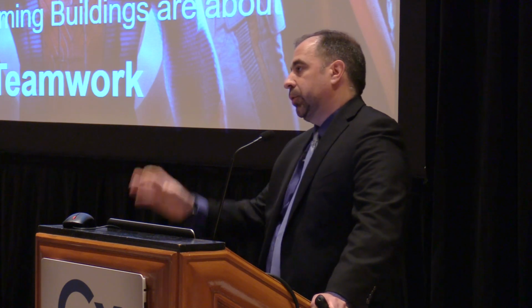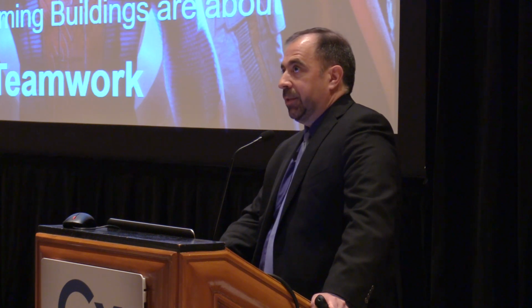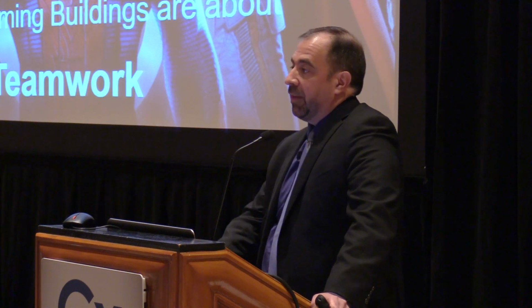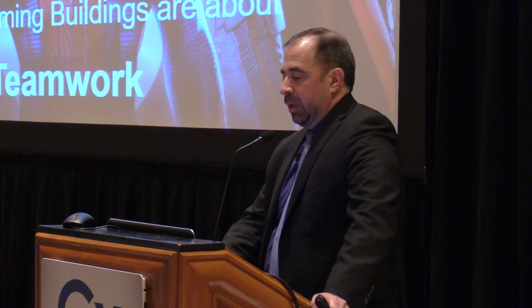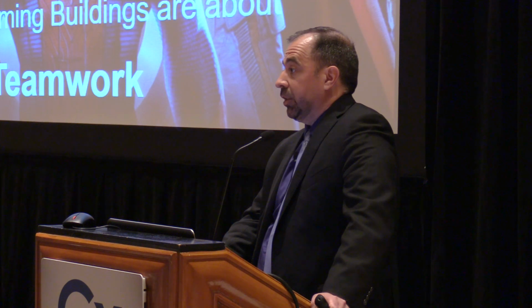ASHE, the American Society for Healthcare Engineering, has an emergency generator testing monograph - it's basically a guide. Are you using anything like that when developing your procedure, like a checklist of everything that needs to be tested? Yes, is the short answer. There's also the health facility commissioning guidelines that ASHE put out, which we reference for what should be commissioned in a hospital. I'm a big fan of that document because they want to test everything under the sun. I haven't referred to it in a while, but inherently we're trying to test to all those things, or at least ask those questions to make sure somebody tells us, no, we don't want to pay you for that.